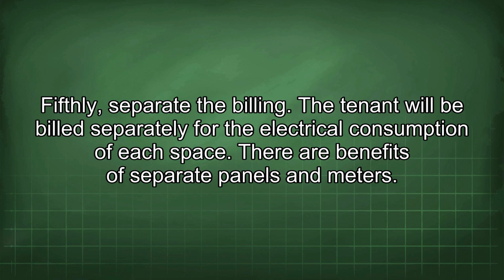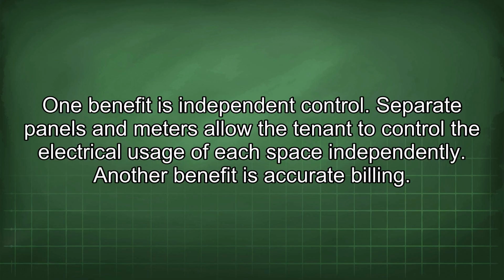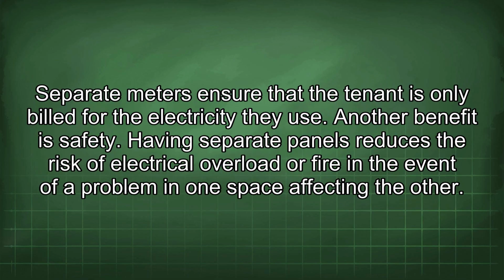There are benefits of separate panels and meters. One benefit is independent control. Separate panels and meters allow the tenant to control the electrical usage of each space independently. Another benefit is accurate billing. Separate meters ensure that the tenant is only billed for the electricity they use. Another benefit is safety. Having separate panels reduces the risk of electrical overload or fire in the event of a problem in one space affecting the other.